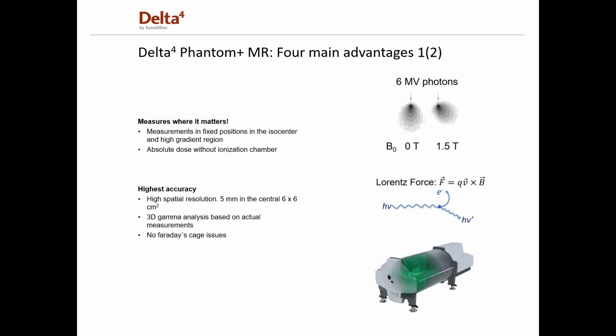So some of the similarities: the MR version Phantom also measures where it matters. So we measure in the isocentric and high gradient regions. We're actually measuring absolute dose. We have the highest accuracy, 5 millimeters in the isocentric area. Same thing holds true here with software where we can merge fields. And the 3D gamma analysis is based on actual measurements. Also important is the fact that we have no Faraday cage issues. When you have diodes around the outside of a cylinder, that can lead to Faraday cage issues.